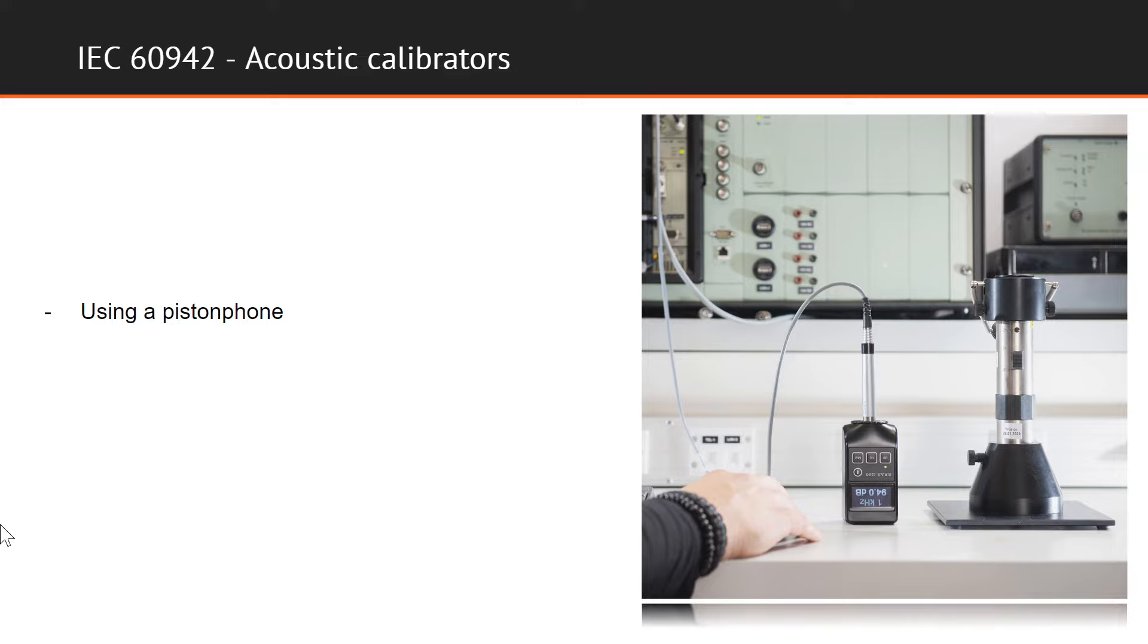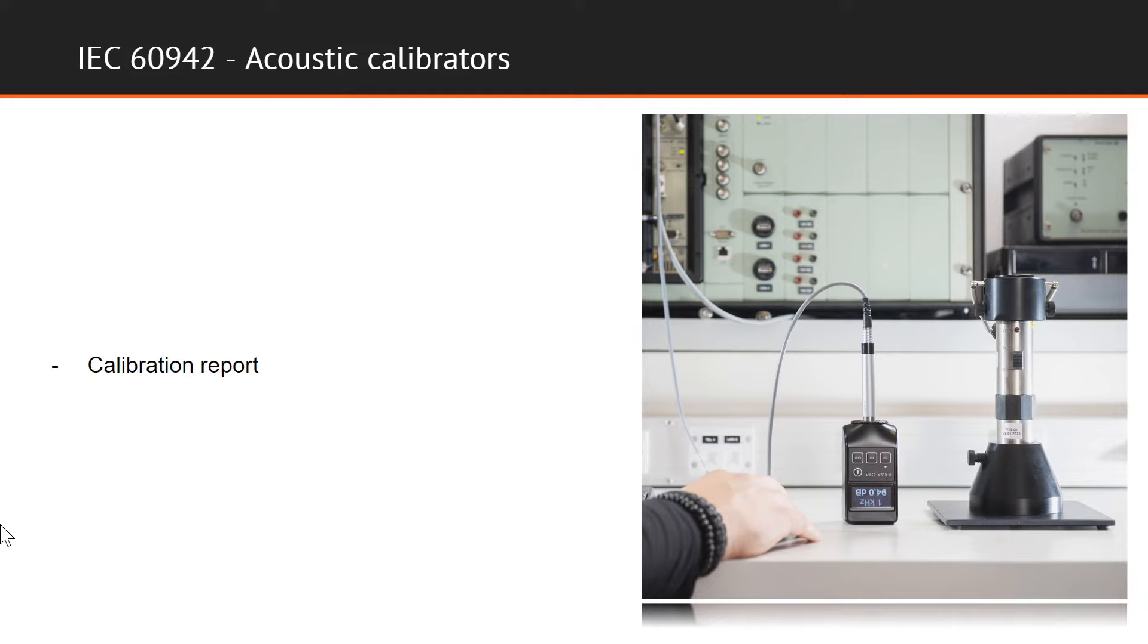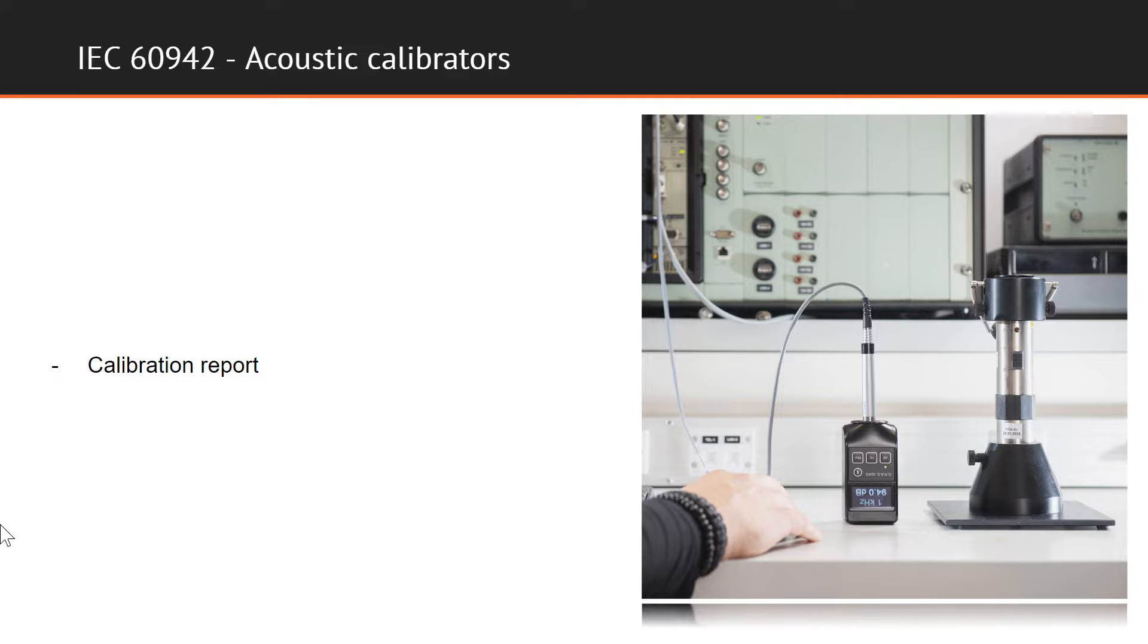The calibration is performed using a comparison method by utilizing the reference piston phone as the standard comparative sound pressure level. The report of the calibration includes measurements of sound pressure level, frequency, and total distortion. If the instrument is equipped with an accessory barometer, this is checked at the current air pressure.